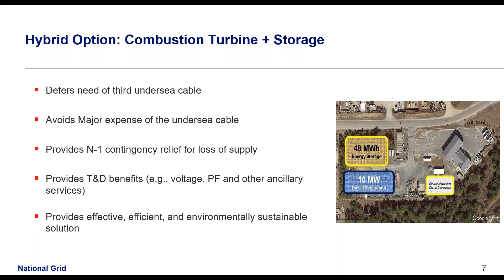With this hybrid option of both the combustion turbine generator and battery, it defers the need for that cable, avoiding that extra expense, and provides contingency relief during a loss of supply. Side benefits include T&D benefits for the local grid such as power quality, voltage, power factor, and other ancillary services, yielding an efficient, environmentally sustainable, and effective solution.